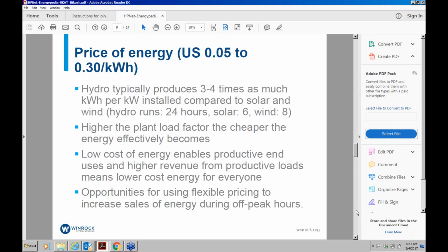Of course, the challenge is how do you use all that energy, because any energy not used is wasted. That 3 to 4 times as much energy doesn't add much value if you can't use it. So the trick, the fundamental thing, is how do you increase the plant load factor of a hydro plant, because the higher the load factor, the cheaper the energy effectively becomes. And because running costs are low, and you don't have fuel or generally even batteries to replace with most hydro schemes, this matters even more.